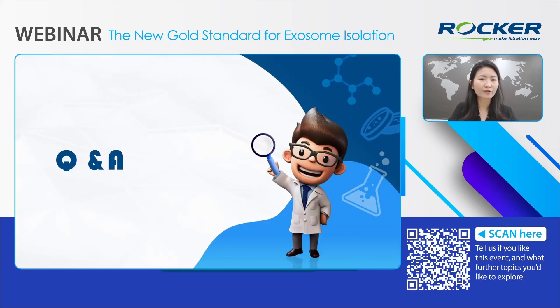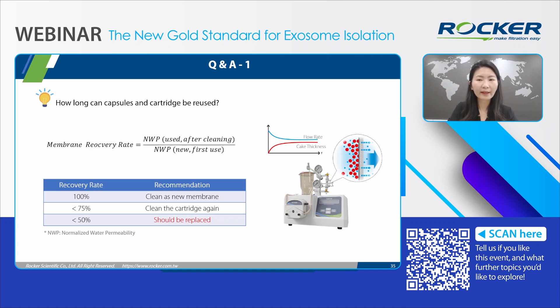That concludes the presentation. Let's now move to the Q&A session — I will take up to three questions. First question: how long can capsules or cartridges be reused? The efficacy of the membrane is evaluated using the normalized water permeability test, the NWP test, which measures water flow at first usage and after cleaning to assess membrane clogging. The more clogged the membrane, the slower the flow rate. If the recovery rate falls below 75%, additional cleaning is recommended. If it drops below 50%, replacement is advised.